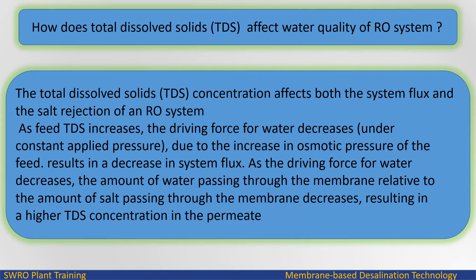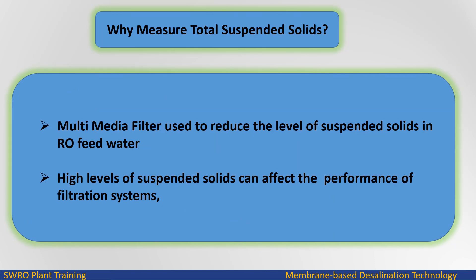The total dissolved solids (TDS) concentration affects both the system flux and the salt rejection of an RO system as feed TDS increases. The driving force for water decreases under constant applied pressure due to the increase in osmotic pressure of the feed, resulting in a decrease in system flux. As the driving force for water decreases, the amount of water passing through the membrane relative to the amount of salt passing through decreases, resulting in a higher TDS concentration in the permeate.